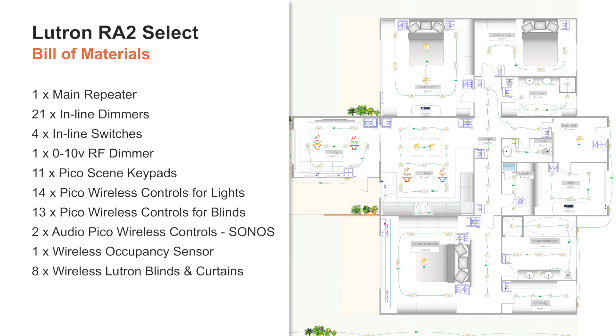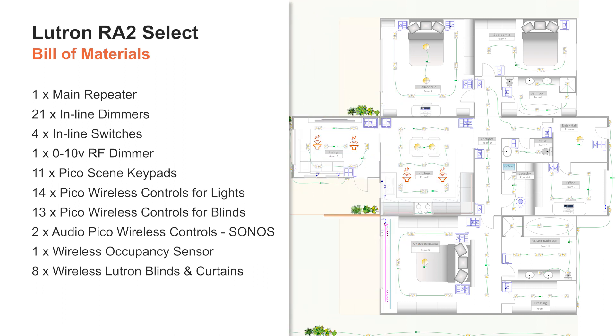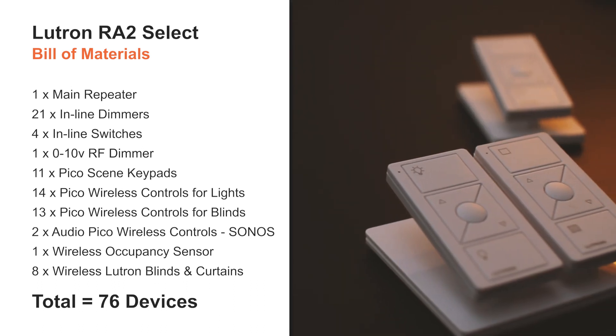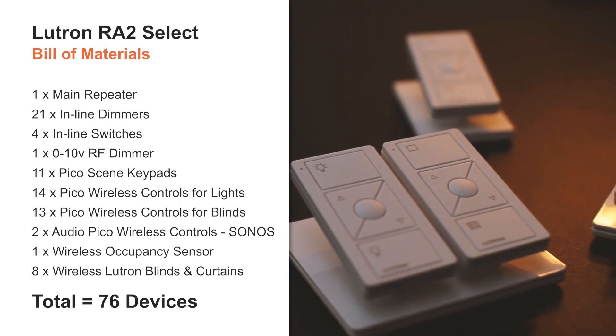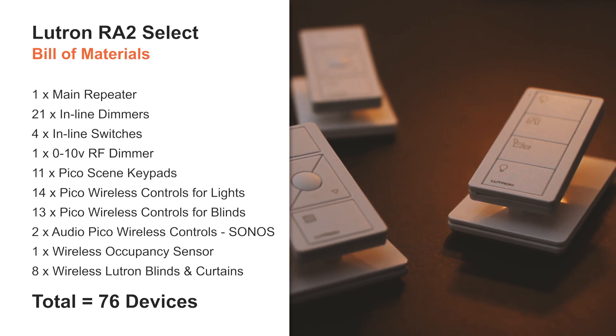The final point here is to remember that a Lutron RA2 Select system can handle a maximum of 100 devices. Knowing that the main repeater uses one, this leaves us with 99 devices to play with. Here we have a total of 76 devices, which to me is perfect, as it gives me enough room to add additional devices in the future — if the client requires additional Picos, additional Lutron motorized blinds, or if we need an auxiliary repeater.